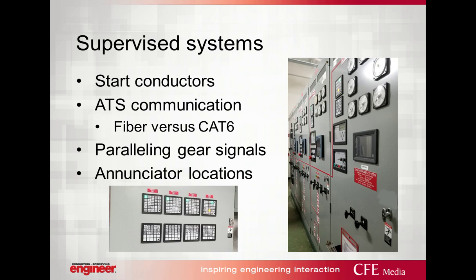You're going to have, of course, either your load shed or load inhibit. That inhibit will be used with paralleling gear to get multiple generators to control, remember those load steps that we talked about previously? Those load steps will be managed through those inhibit and load shed signals. And lastly, your annunciator locations are going to vary throughout the facility. You're going to coordinate that with your facility.